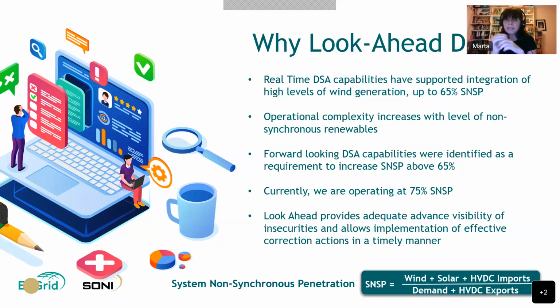Based on experience and on intensive offline studies, we identified that in order to confidently increase the SNSP level above 65%, we needed forward-looking capabilities. We needed dynamic security assessment not only in real time, but also in the incoming hours. That would give us the time to get ready and implement the most effective corrective action in a timely manner, and identify which is the most cost-effective as well.